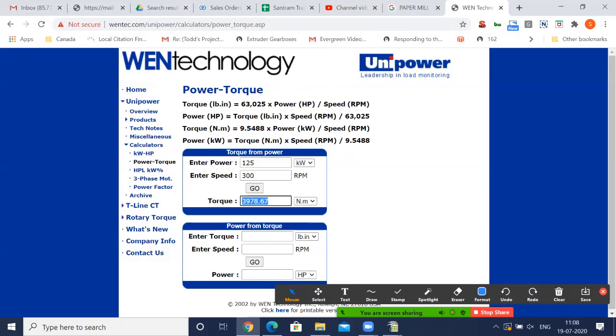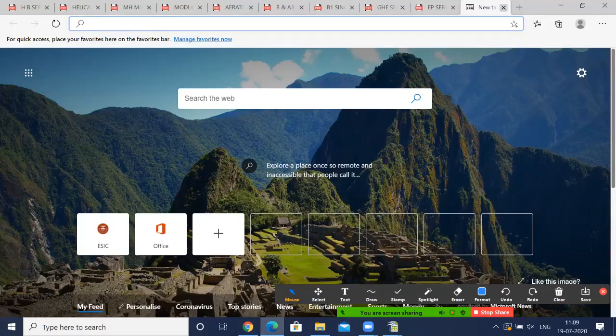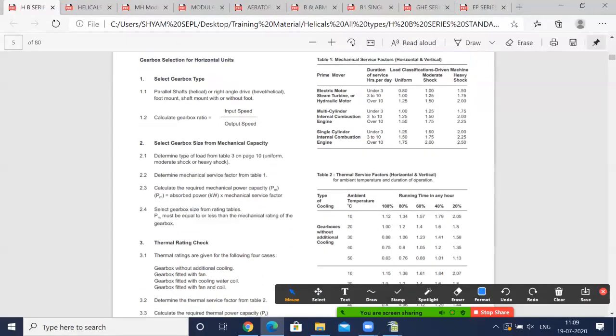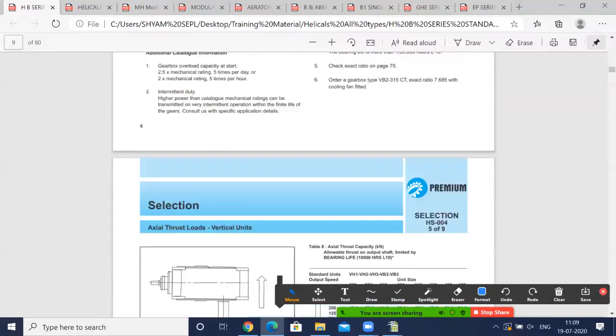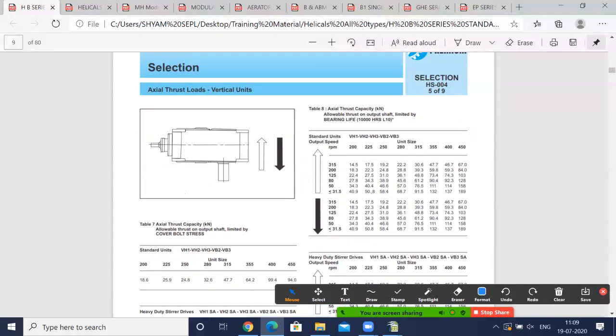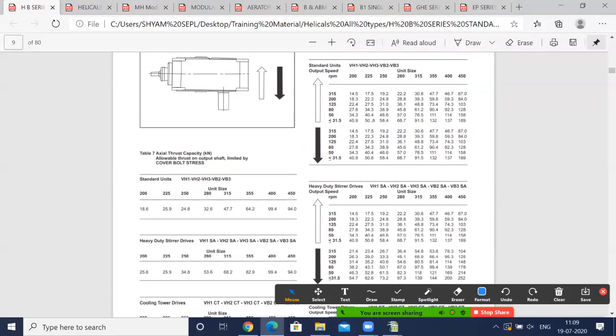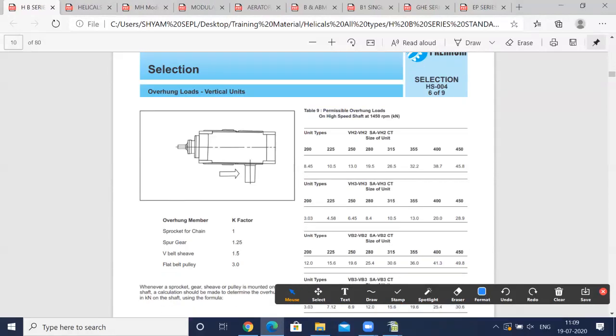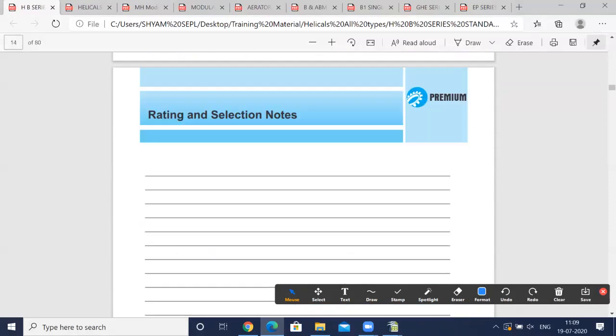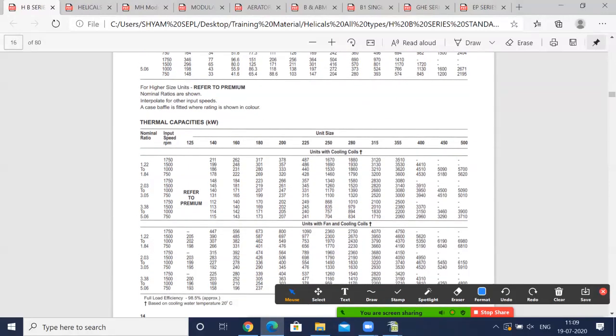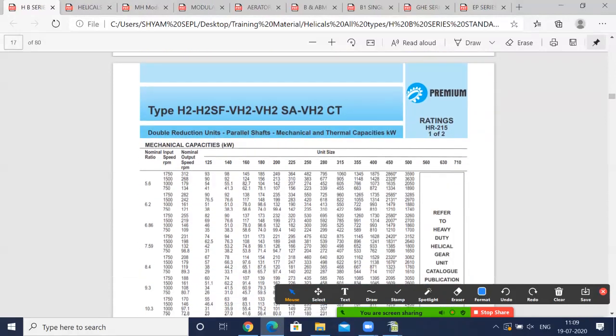So based on that, even if you consider the torque-wise safety factor, it is 3978 divided by 2300. So your gearbox is safe. That is how your selection is done, and that is how we have selected the first gearbox, H1. If the speed required is lower, and they require like 100 rpm, you have to do nothing else. You just need to go from H1 to H2, because ratio-wise the model will increase, so it becomes a two-stage gearbox. So H2 is standard.